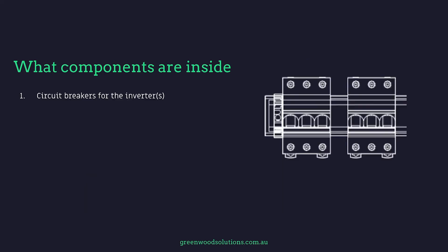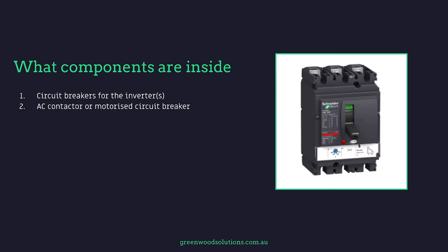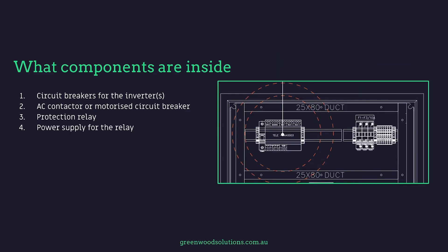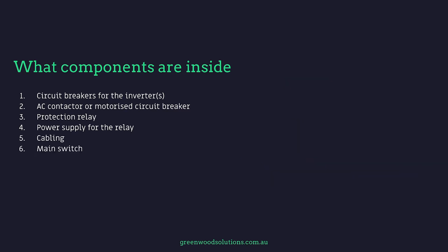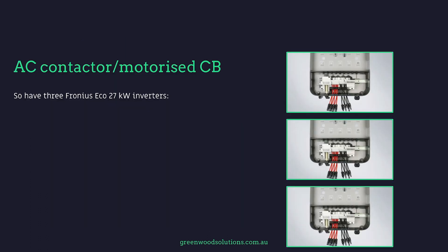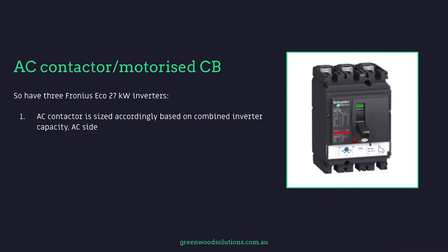So what components are inside? Well, there's a circuit breaker for the inverters, an AC contactor or motorized circuit breaker, a protection relay, a power supply for the relay, cabling, and a main switch. For example, say we have three Fronius Eco 27 kilowatt inverters — we'll need three corresponding circuit breakers in the secondary protection board, say 50 amps each. But as the designer installer, you select these. The AC contactor is sized accordingly based on combined inverter capacity on the AC side.